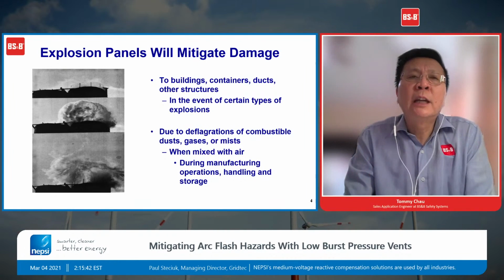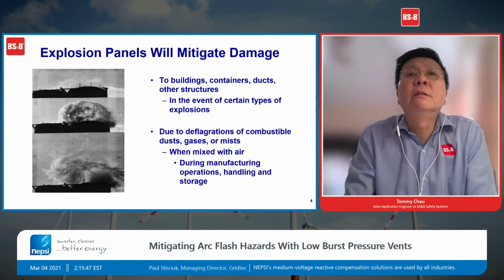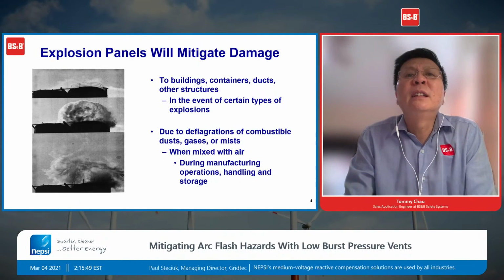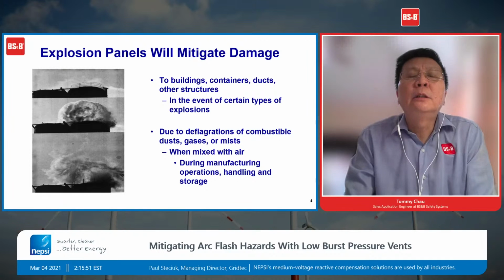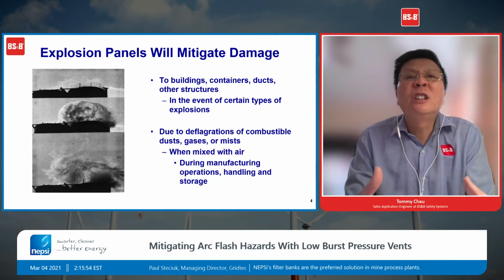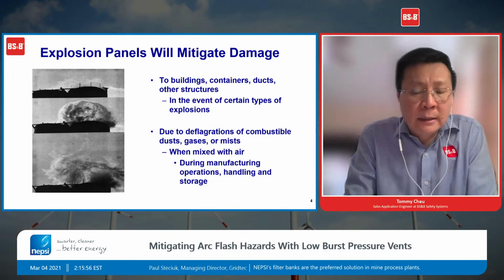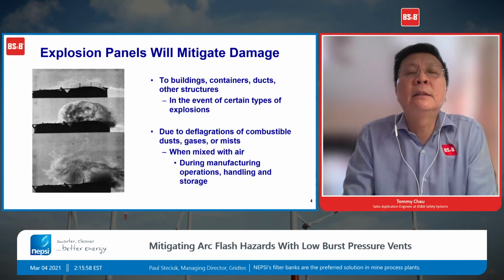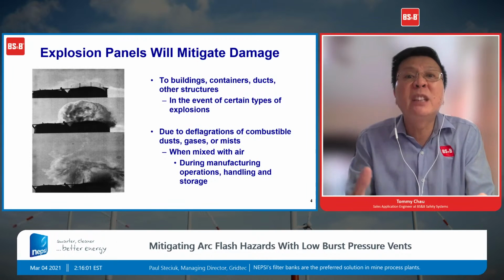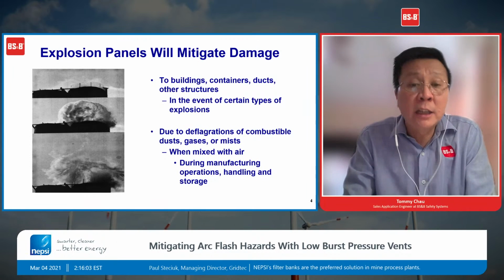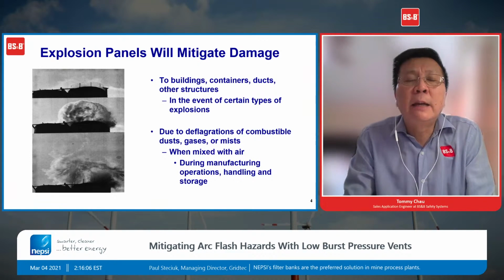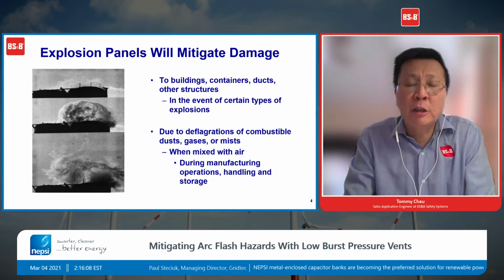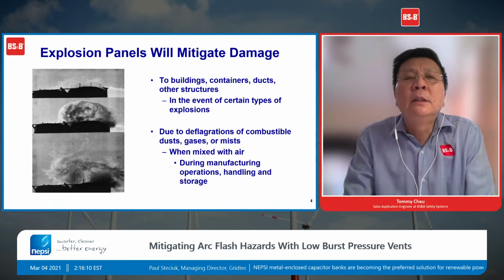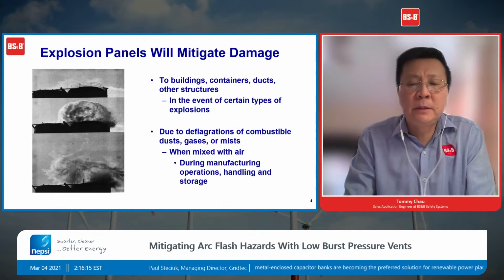Okay, so again, explosion panel will mitigate and minimize the damage to your equipment in the event of a deflagration. Typically, when you have a deflagration, it's due to some manufacturing operation, handling of the equipment. It's when you have air mixed inside the product, and you can have an ignition, and then you have the deflagration. So typically, it could happen during operation and handling of the equipment.